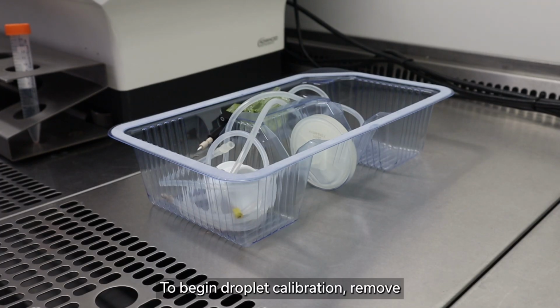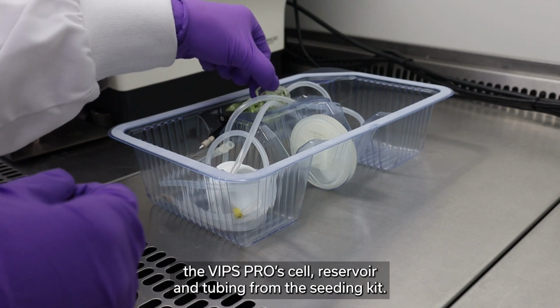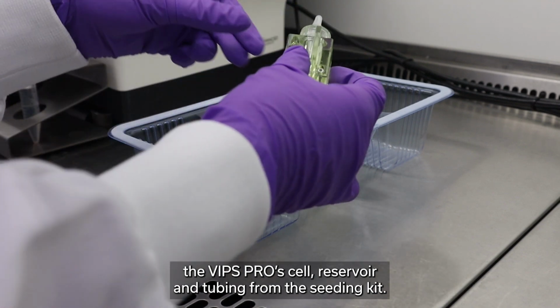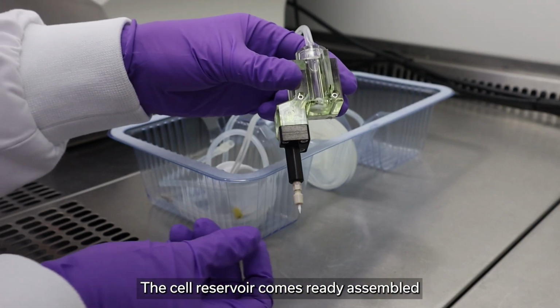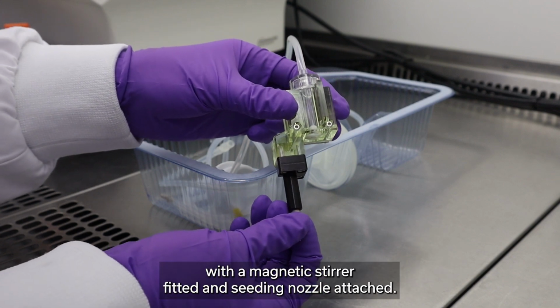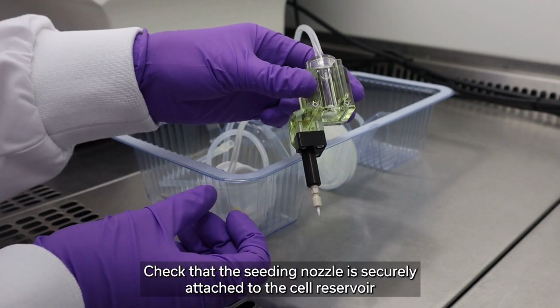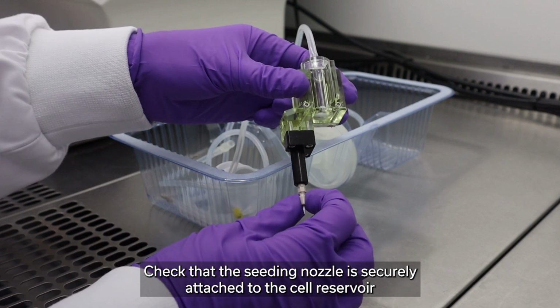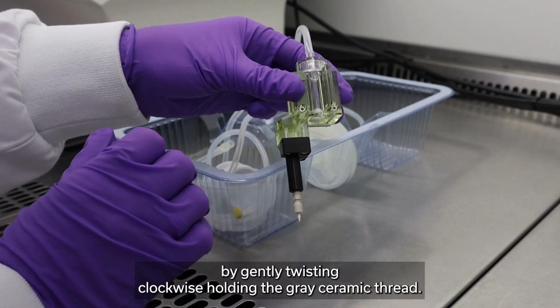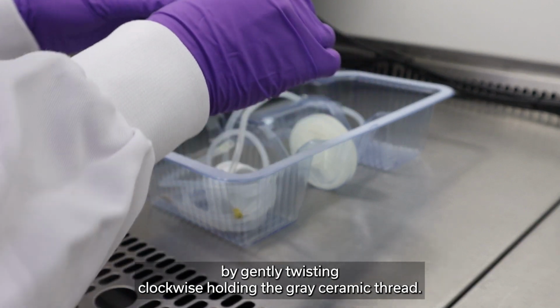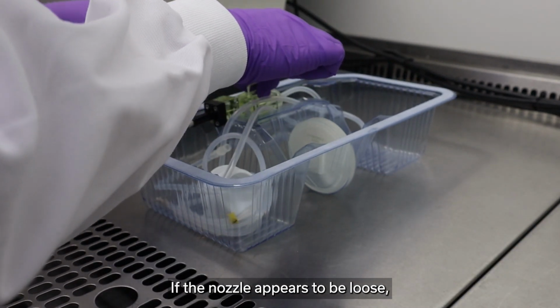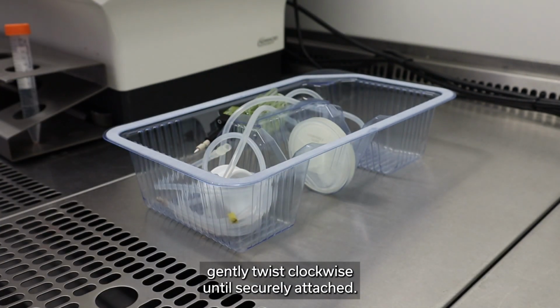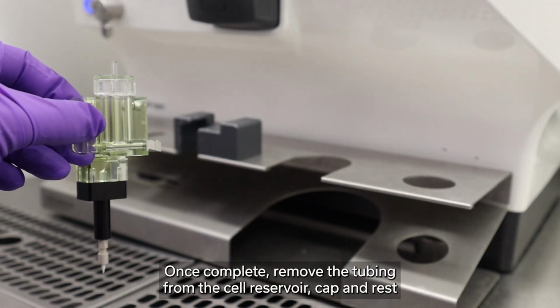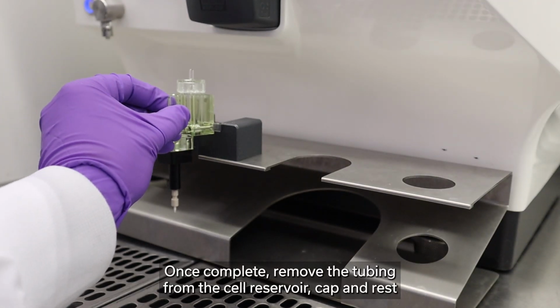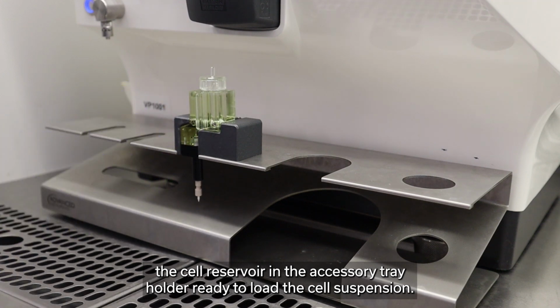To begin droplet calibration, remove the VIPS Pro's cell reservoir and tubing from the seeding kit. The cell reservoir comes ready assembled with a magnetic stirrer fitted and seeding nozzle attached. Check that the seeding nozzle is securely attached to the cell reservoir by gently twisting clockwise, holding the grey ceramic thread. If the nozzle appears to be loose, gently twist clockwise until securely attached. Once complete, remove the tubing from the cell reservoir cap and rest the cell reservoir in the accessory tray holder, ready to load the cell suspension.